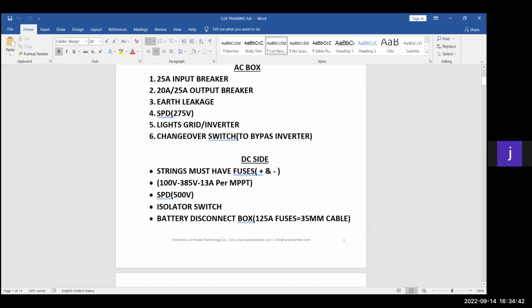So firstly, I have a 25 amp input breaker that I recommend the clients have. You can enter whatever size you would like here. I have a 40 amp bypass current that this machine can handle, but I will never go higher than 5 kilowatts worth of power. That's between 20 and 25 amps that you can reach that power. Reason being is if you are in bypass mode and you're pulling 6 to 7 kilowatts through my machine and Eskom fails at that moment, your machine will go into a direct overload, EPS overload. So that's why I won't go that high.